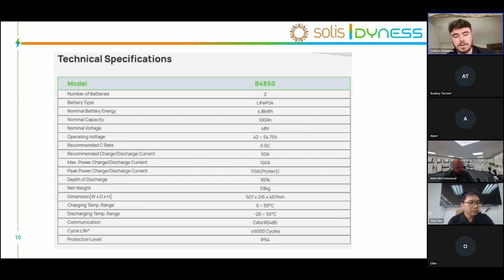Especially in some solar and battery projects we've seen, they need a 5 kilowatt hour and then a 7.5 kilowatt hour. So we can do that with this. It allows for that flexibility on a very minute scale. These are rated for 6,000 cycles over their warranty period, and 95% depth of discharge, which is market leading, especially for a module of this size. So it's a very, very good module.